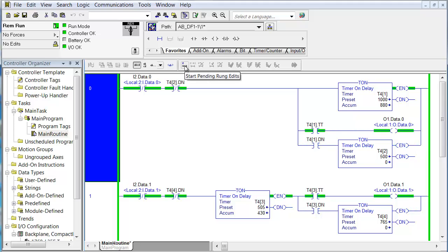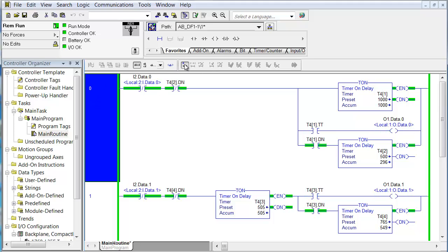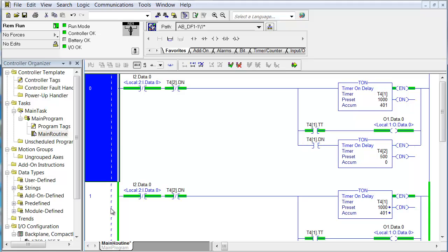Online editing: if you mouse over, start pending rung edits, accept pending rung edits, cancel pending rung edits, assemble rung edits. In the old days it was a three-step process of accept, test, and assemble. When you put a rung in edit mode, you see two rungs — one marked R for run, one marked I for insert. You can edit the insert rung, accept it, then test it. When in test mode, the processor executes the edited rung instead of the original.